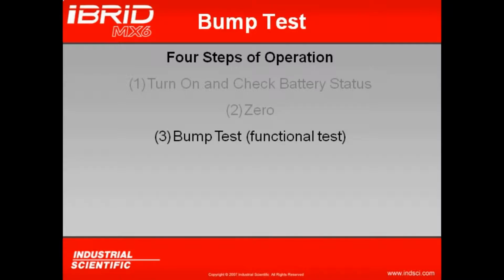The third thing we're going to do with the instrument before we use it is we're going to take it through a functional test, otherwise known as a bump test. What a bump test is designed to do is to verify sensor and alarm operation. By applying calibration gas or bump gas, the instrument is going to be challenged by the gas to ensure functionality, ensuring that the sensors do see gas, and when they see the gas, that they go into alarm. This should be done before each day's use.